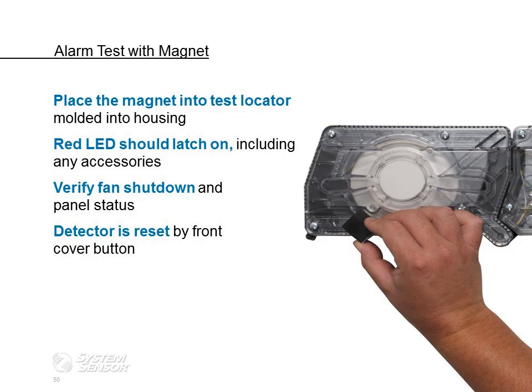We also have an alarm test with a magnet. To test the detector with a magnet, place the magnet on the test locator. It's molded into the housing, so you can see it. The LED is going to latch on. Once that LED latches on, that's basically indicating it's an alarm. The relays are going to change state. We need to verify that the fan shut down, and then you can reset the detector by pressing the reset button on the front cover of the detector.